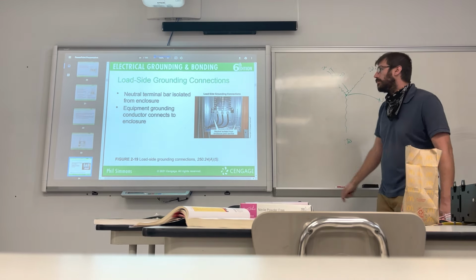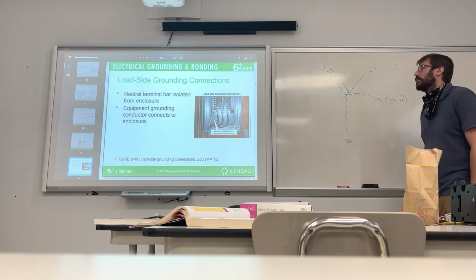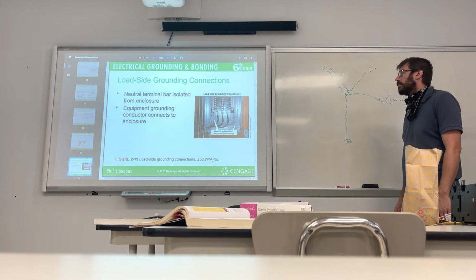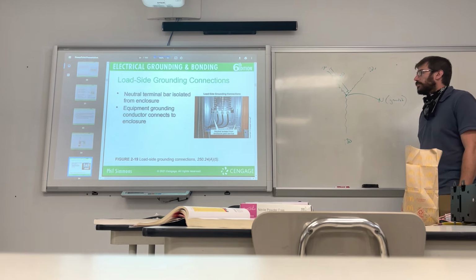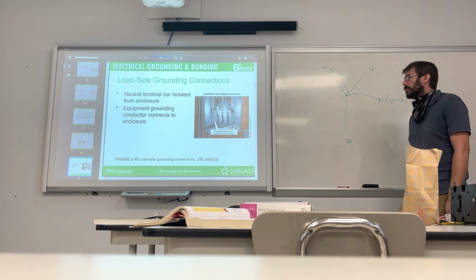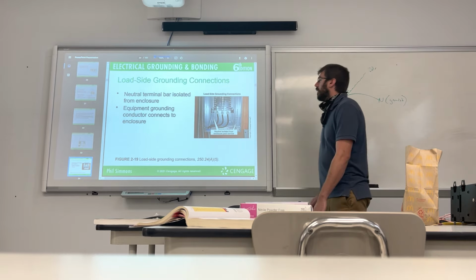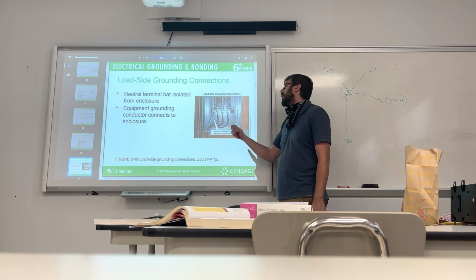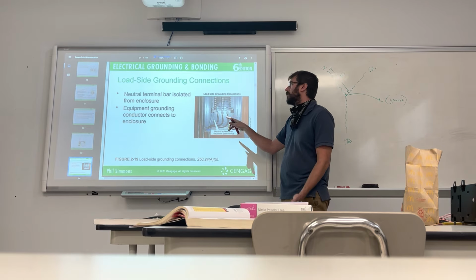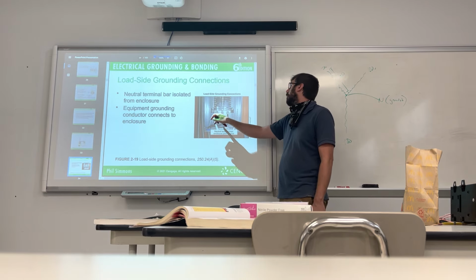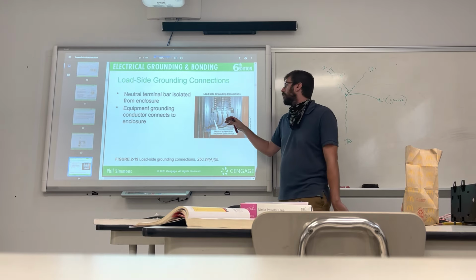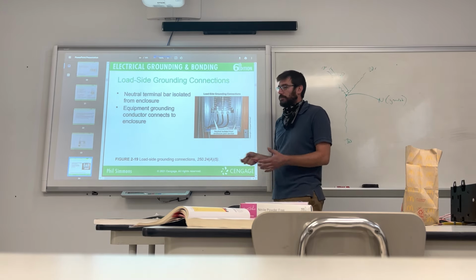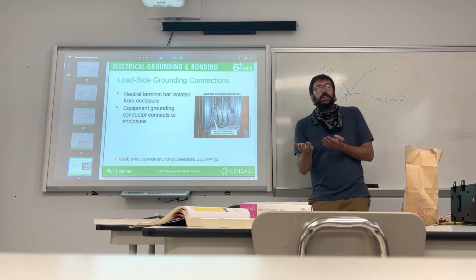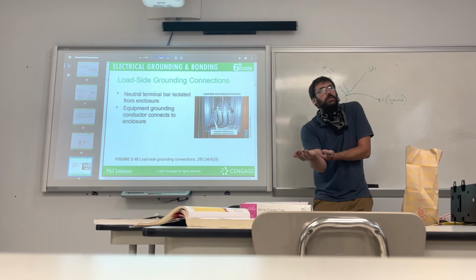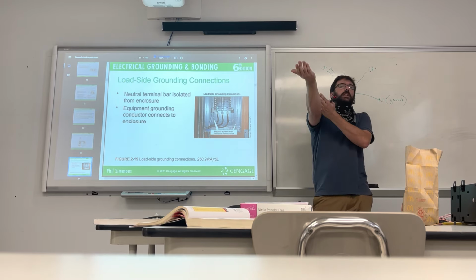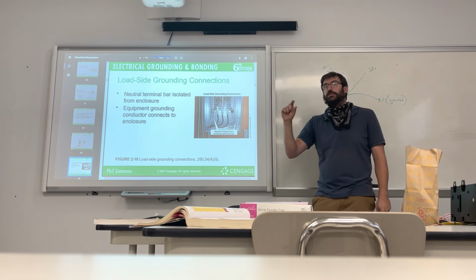That's fine. Load side grounding connections: neutral terminal bar isolated from enclosure, equipment grounding conductor connects to enclosure. All right, so this main panel box, I would consider this to be a sub panel then. But that neutral bar, it shows up really close for the first time. The neutral bar has a bit of plastic underneath it, and it's actually off the enclosure. It's isolated off the enclosure by an inch or two.